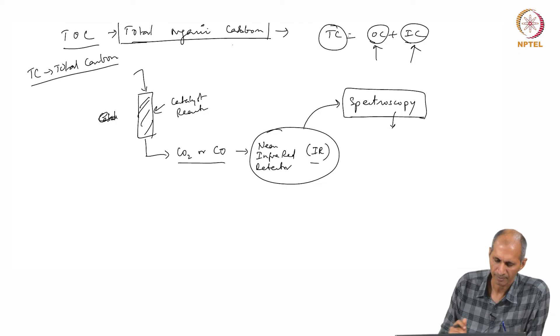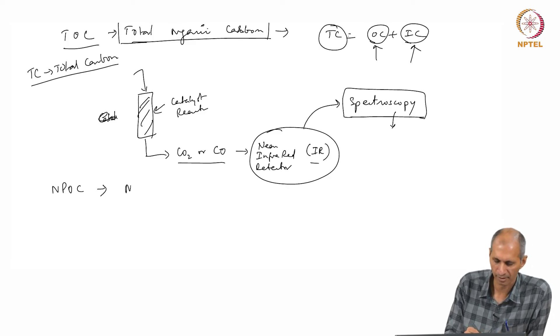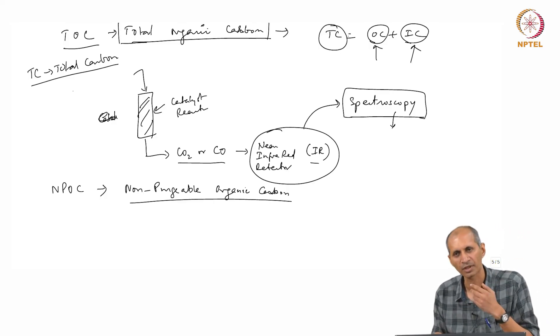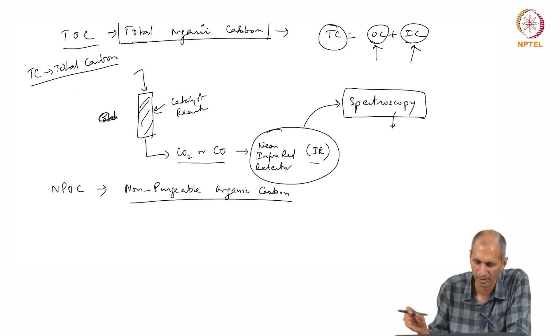In this, there is another category called NPOC, which is called non-purgeable organic carbon. What this means is that you are still doing the same thing—adding a sample—but before it goes in, you purge your sample. Any volatile organic compounds are all gone; they are taken away. Whatever is there is the non-volatile part, which is then sent through that catalyst, and then carbon dioxide comes out.